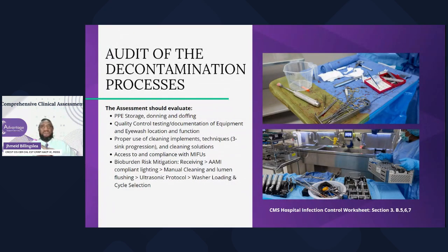Now we're back to decon, right? And you're like, wait a minute, this is not decon. Why do we have a picture of the OR? Because point of use treatment, it's not cleaning instruments. Let's stop using that term, cleaning instruments. Point of use treatment is leaving instruments in the condition of next use.